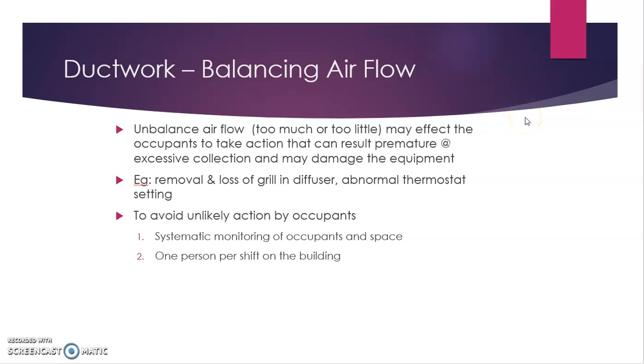So before we go into the ducting cleaning or maintenance, we have to look into the balancing of airflow from the ducting. Some ducting systems are usually not balanced enough. So usually the balancing must be done before we come into that building, and usually the balancing of airflow will be done during the testing and commissioning period. So what is the purpose of balancing of the airflow?